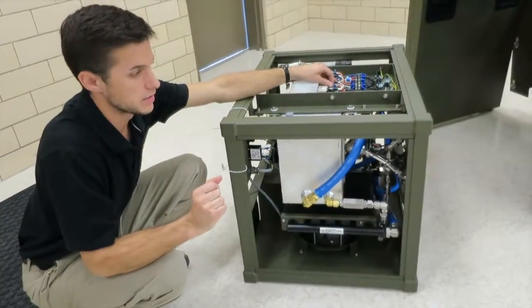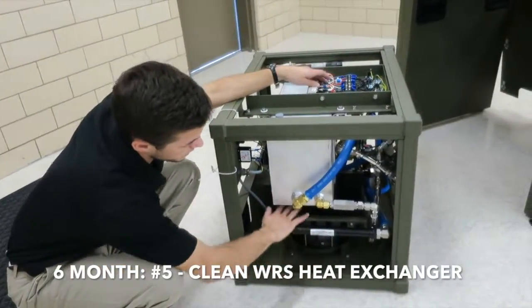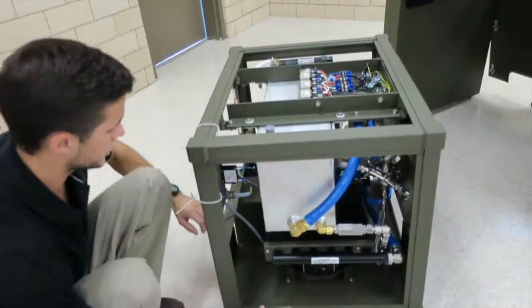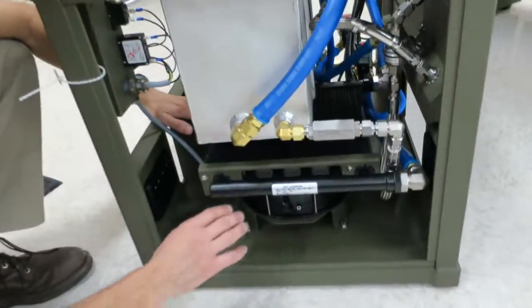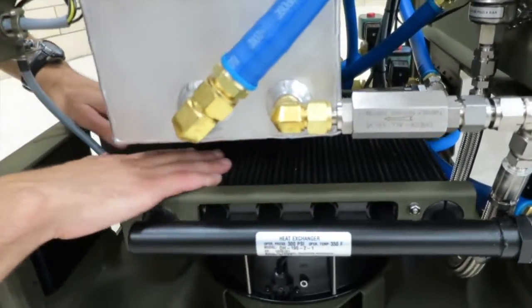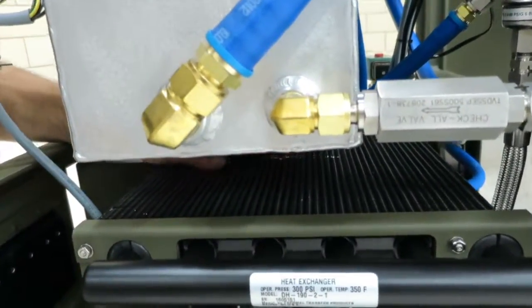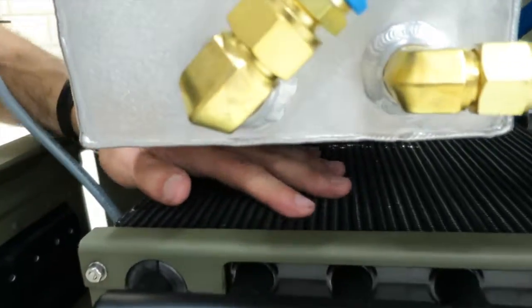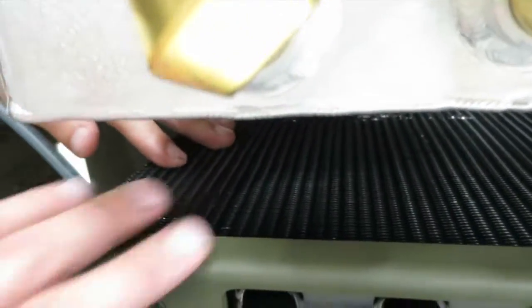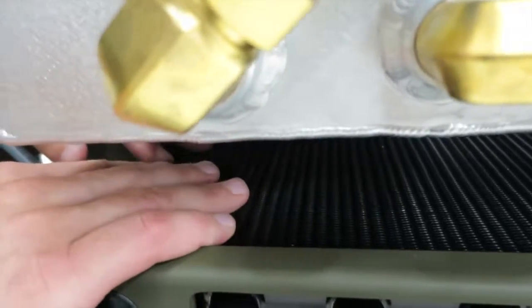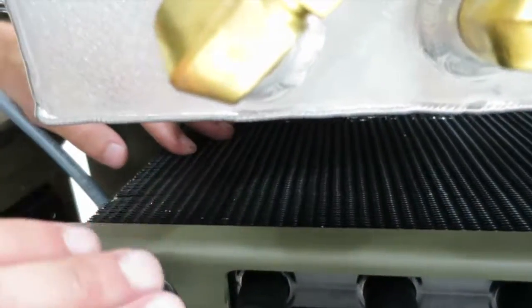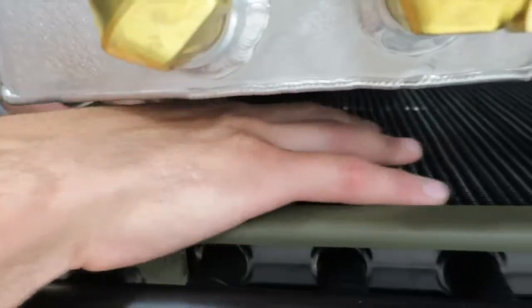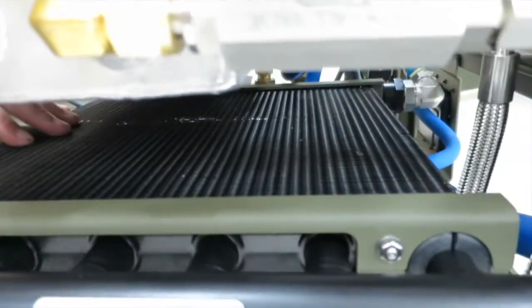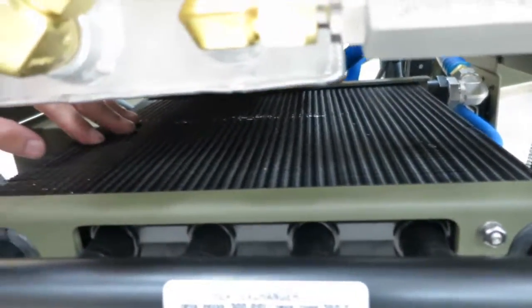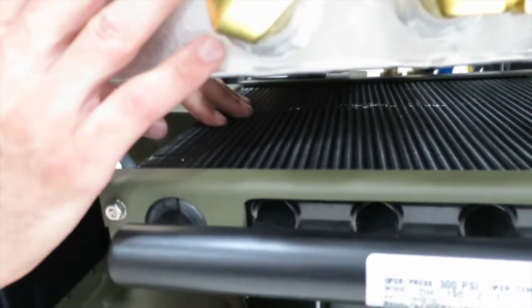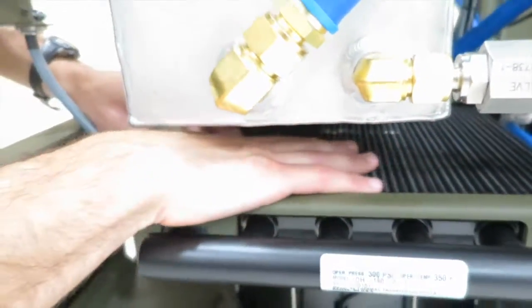So you're going to want to have the panel off, and you'll see that we've got this heat exchanger right down here. And all these little aluminum fins right here, after a lot of use, can get gunked up with some dust and dirt. So if these are starting to get gunked up upon inspection, you're going to want to rinse this out and really clean it well. If you don't have good airflow, then it's not going to be able to cool your water nearly as well sitting in this tank. So you're going to want to inspect and keep these things clean.